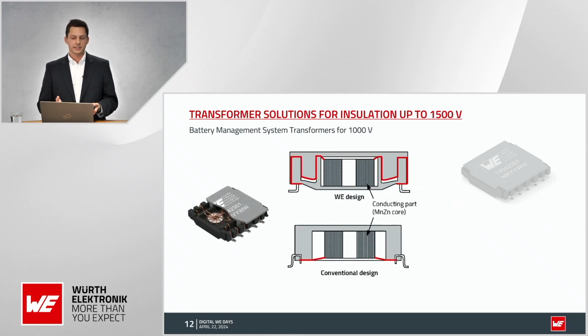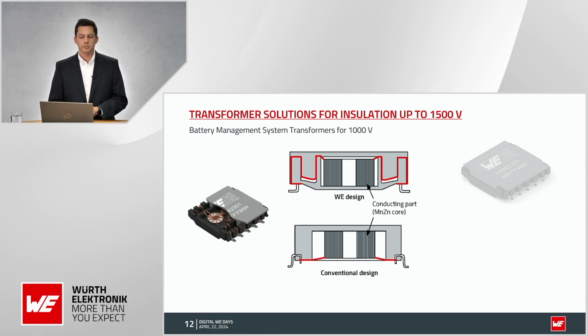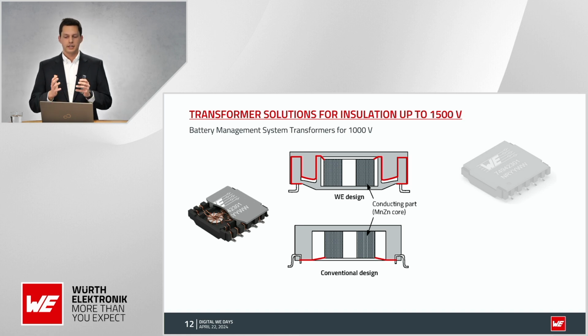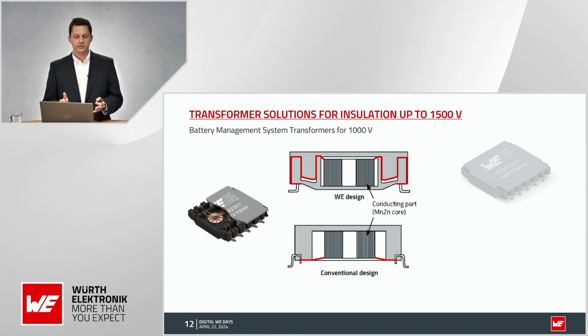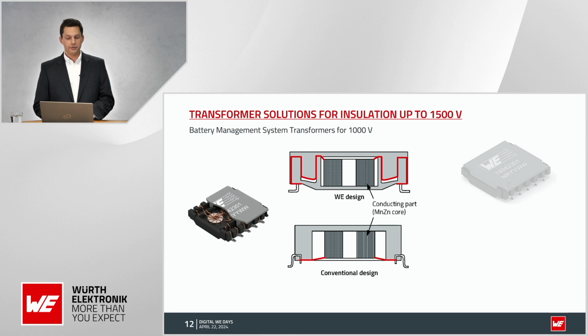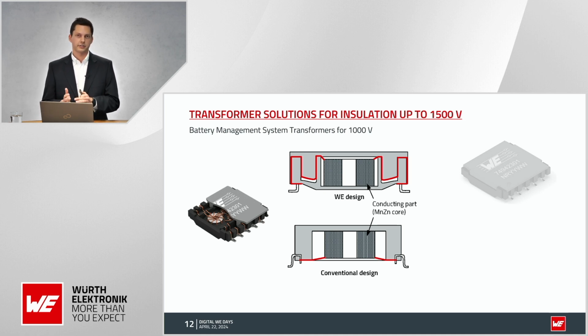One specialty is that they have high clearance and creepage distances, which are achieved through a special housing design. You can see this, compared to other products on the market, in the shown picture. The main reason for this design is the manganese zinc core, which reduces the creepage and clearance distances. Therefore, we use the special design to get high physical creepage and clearance distances in a housing with small outer dimensions.